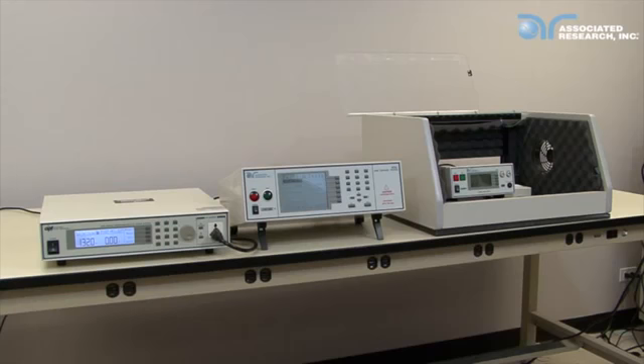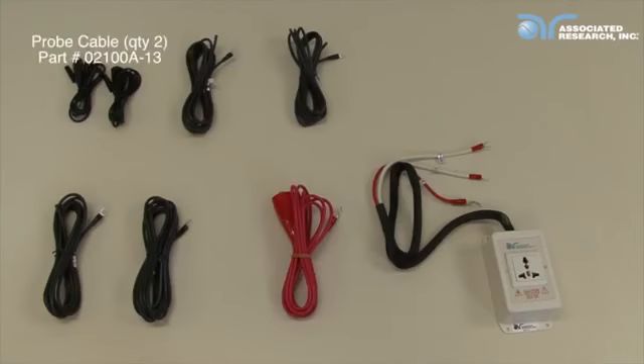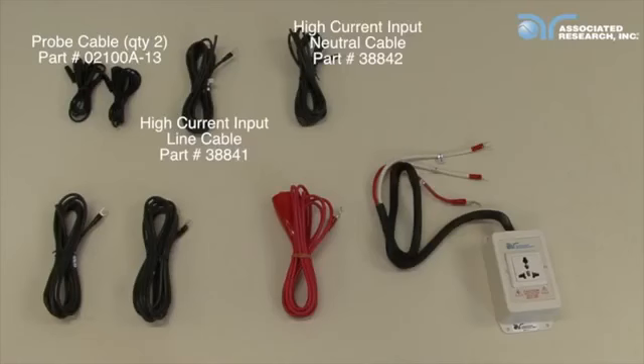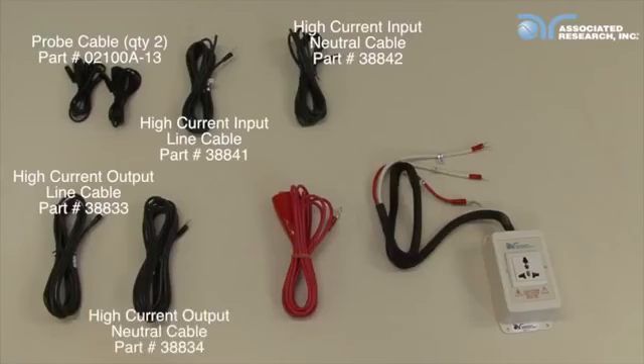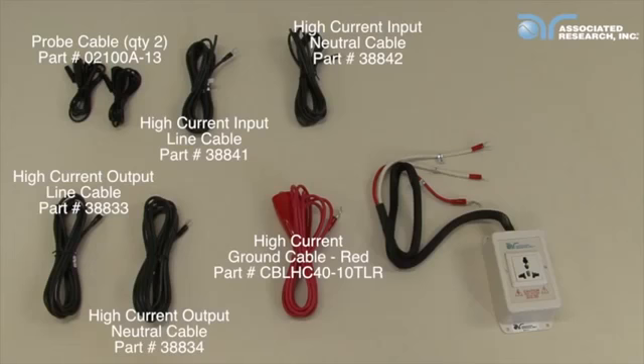In order to connect the 620L to a power supply and the DUT, you will need the following accessories: 2 probe cables, a high current input line cable, a high current input neutral cable, a high current output line cable, a high current output neutral cable, a high current ground cable, and an adapter box.